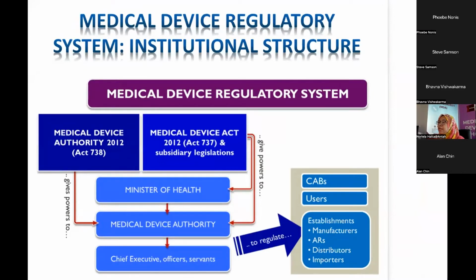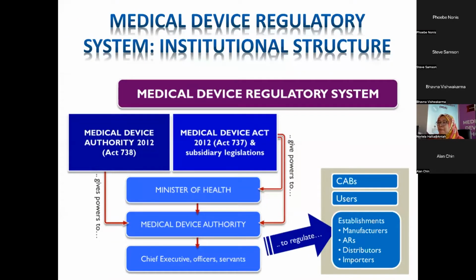Okay, so as you see on the slide, in Malaysia, there are 2 acts that have been passed in Parliament of Malaysia that are related to the control of medical device and its industry in our country. The first act is the Medical Device Authority Act, or Act 738, that gives power on the formation of our office, which is Medical Device Authority, and the appointment of our board members. The second act is Medical Device Act 2012, or Act 737, that gives power or enabler to us in regulating the conformity assessment body, which is the third party like notified body in European country. This CAB plays a role in conducting the conformity assessment procedure for the purpose of medical device registration and establishment licensing. This act also regulates the user who is using the medical device on the third party.